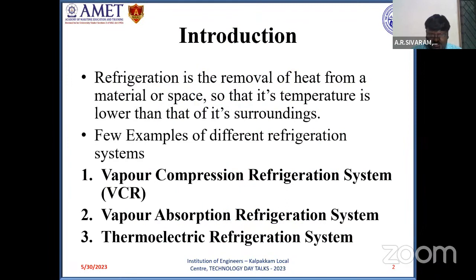Refrigeration is nothing but the removal of heat. It is a process by which a particular material or space is maintained at a lower temperature than the outer ambience or surroundings. Examples of refrigeration systems are the vapor compression refrigeration system, the vapor absorption refrigeration system, the thermoelectric refrigeration system, and so on. For almost 90% of practical applications, we go with the vapor compression refrigeration system. As the name implies, it has a compressor, and that is why it is called a vapor compression refrigeration system, shortly denoted as VCR system.